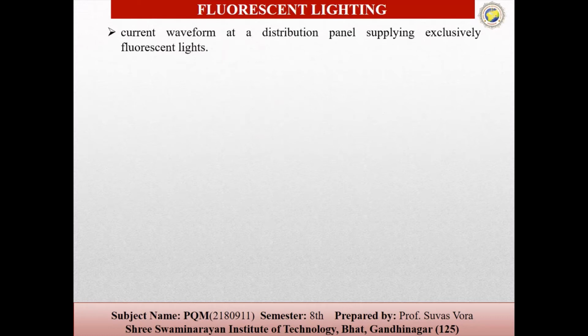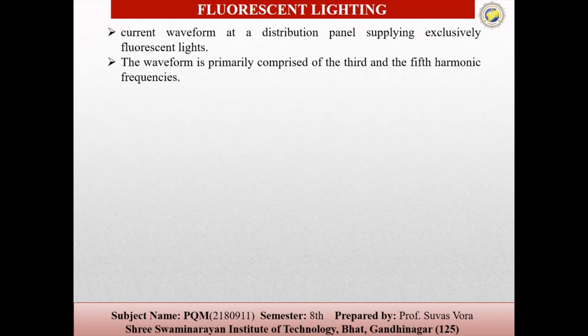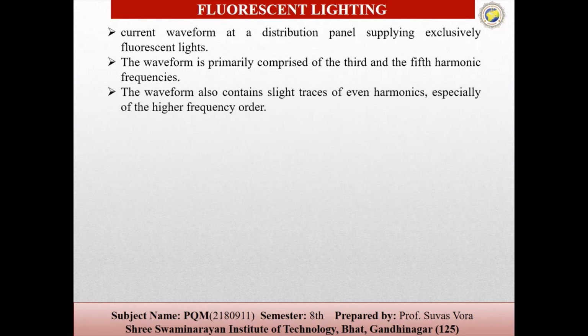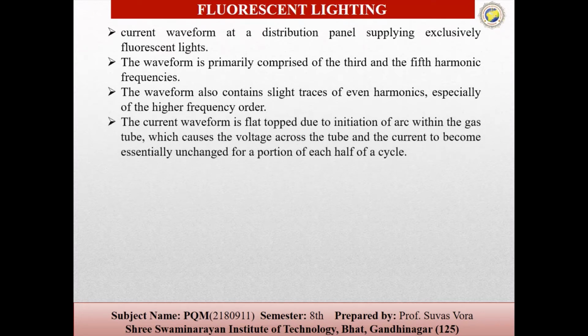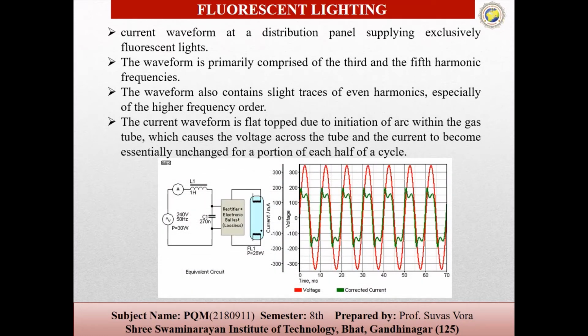So there are two categories of ballast, the electronic and magnetic. So the magnetic ballast is nothing but a transformer with the magnetic capacitors between the primary and secondary winding, and this magnetic ballast can drive a minimum of two lamps with the frequency of 50 Hz. So the waveform is primarily comprised of the third and the fifth harmonic frequencies, and the waveform also contains slight traces of even harmonics, especially of the higher frequency orders. So the current flow is flat-topped due to the initiation of the arc within the gas tube, which causes the voltage across the tube and the current to become essentially square. So these are the actual effects on our power system.